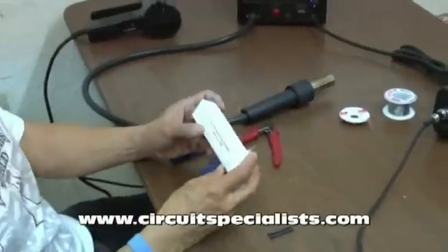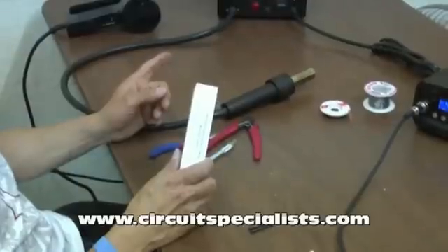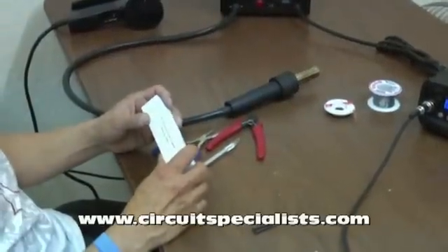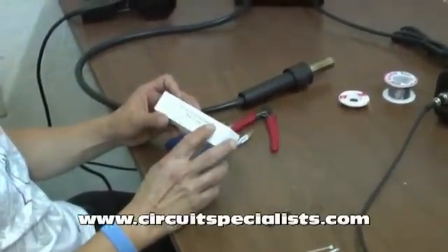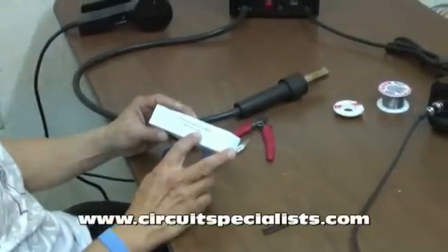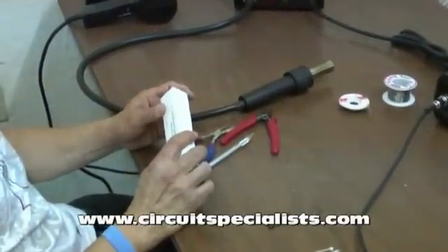The heating element itself is Model 10094. Each station has its own heating element, but this heating element is good for a couple of rework stations, so be sure to make sure you've got the correct heating element on hand before you begin this replacement procedure.